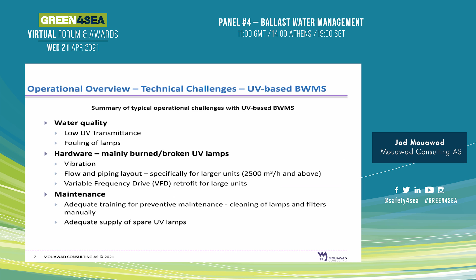Then I recommend putting a variable frequency drive on those large pumps to control the flow rather than controlling it with a valve, because that's creating large forces on the pipes and breaking them. Spare parts, adequate training - same for all equipment. That's important to keep in mind.